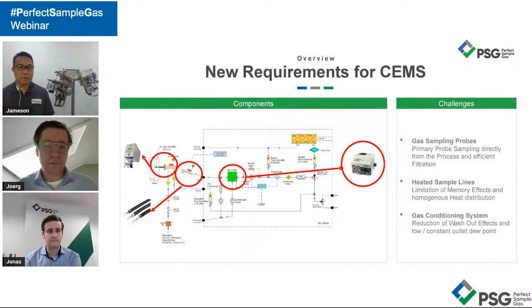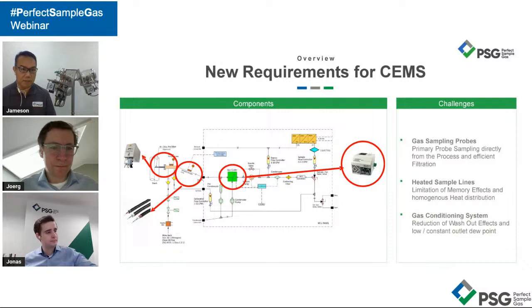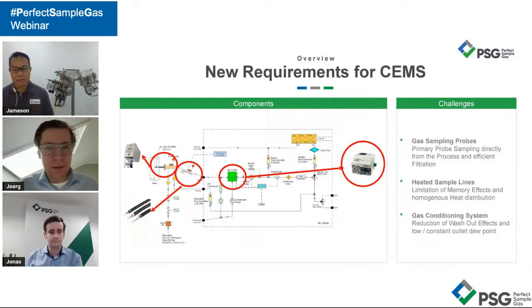We have to heat up the sample, bring it above the water and above the acid dew point, by means of a heated sample transport line. Then we bring it all the way to the gas cooler. And this is the area where, in system integration, a lot of people make a lot of mistakes. Make sure that the entry to the gas cooler is kept to a maximum of only 20 centimeters, meaning that the heated sample line, which is so hot at 180 degrees, above the SO2 dew point, meets the gas cooler at 3 degrees C.